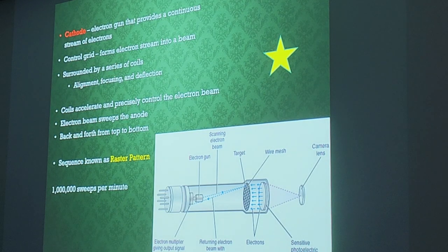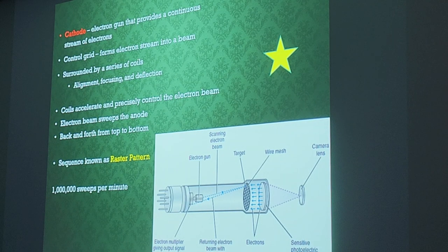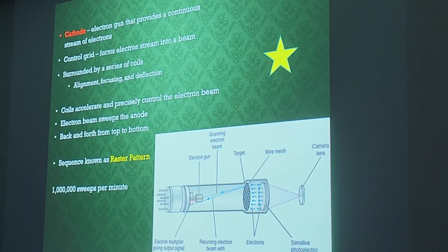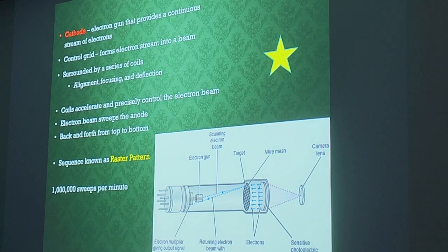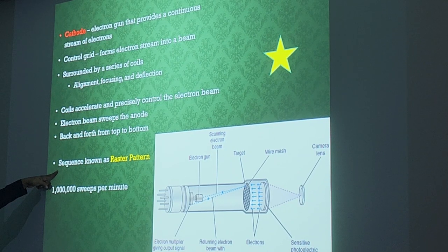The electron gun provides a continuous stream of electrons aimed at the target. The cathode is surrounded by coils that accelerate and precisely control the electron beam. The electron beam goes toward the target in a special sweeping zigzag motion from top to bottom known as the raster pattern — approximately one million sweeps per minute.